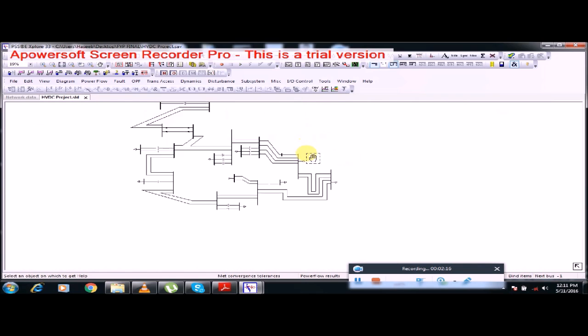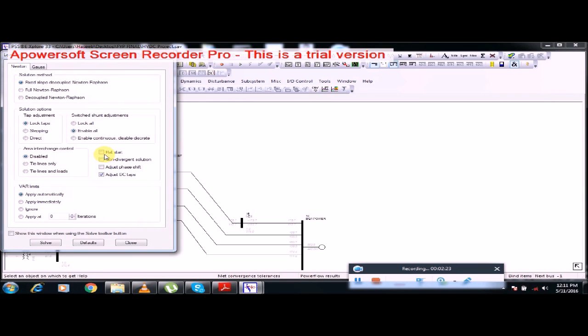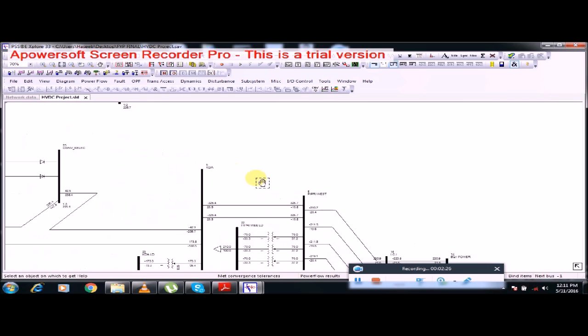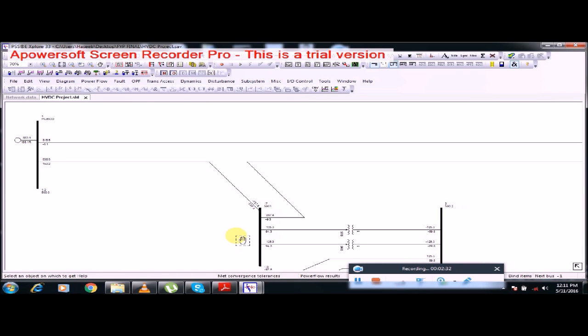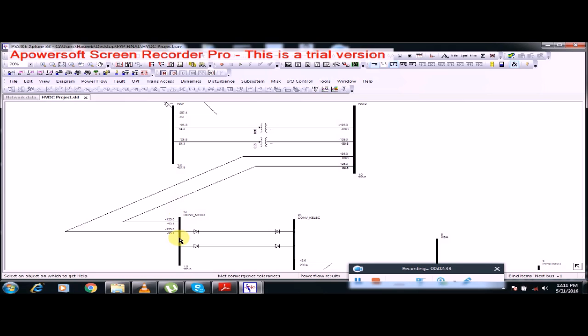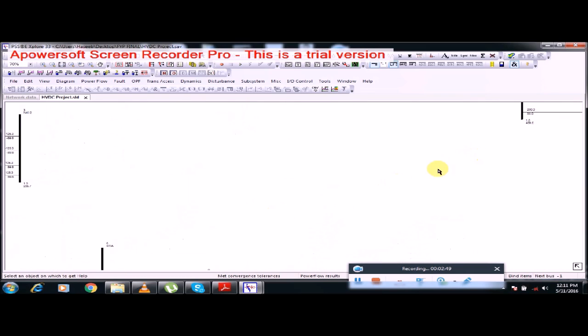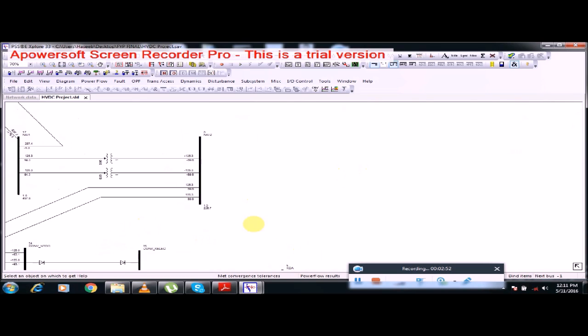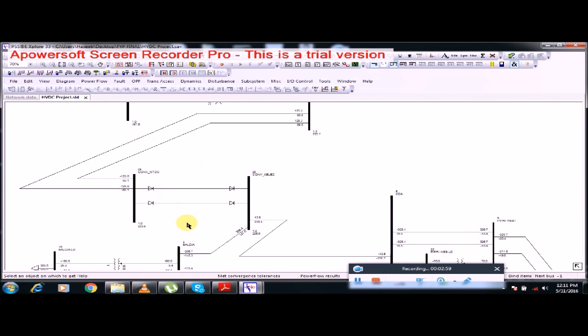The single line diagram of our system after incorporation of the HVDC link is now shown. The NTDC utility terminates at the converter NTDC-24 bus. The interconnection is made through the HVDC link, which consists of two DC lines, after which the K-Electric utility starts. The connection between the Jamshora bus and the KDA bus has been broken so that power can only flow through these two HVDC-connected buses.